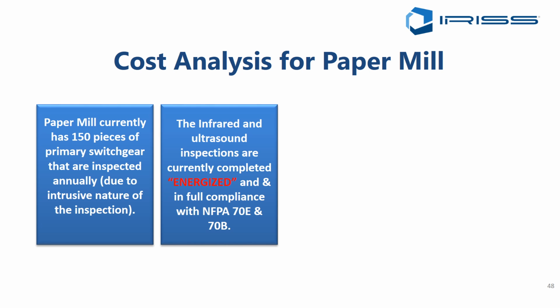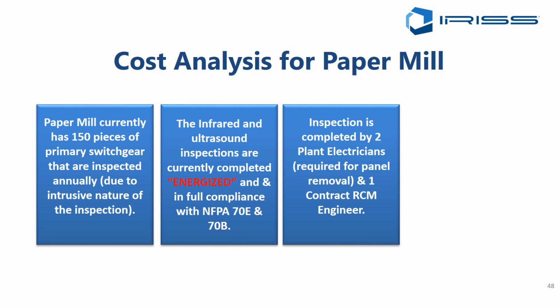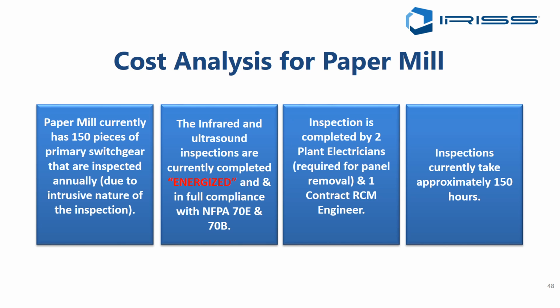The infrared and ultrasound inspections were completed energised and in full compliance with NFPA 70E and 70B. They were completed by 2 plant electricians required for panel removal, and one contract RCM engineering company that did the infrared and ultrasound inspections. The inspections currently take approximately 150 hours to complete.